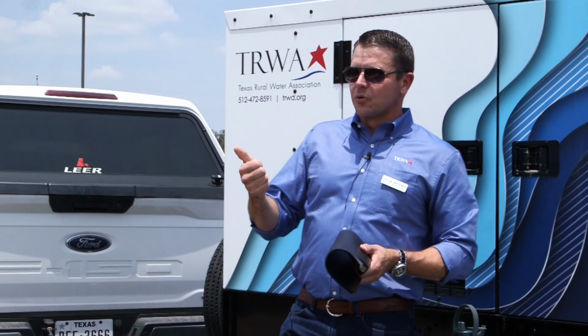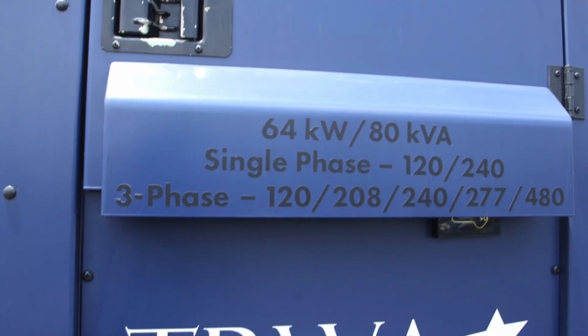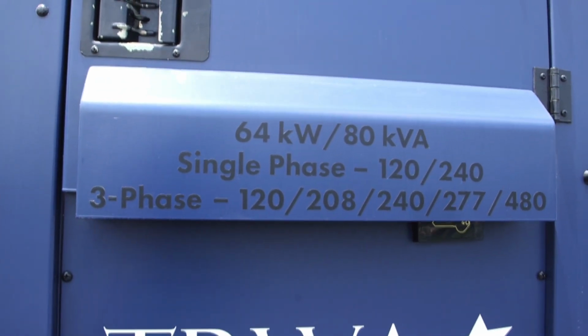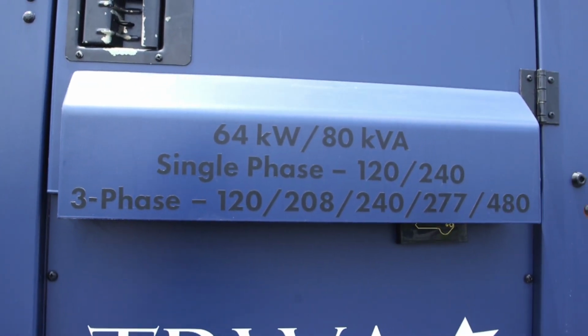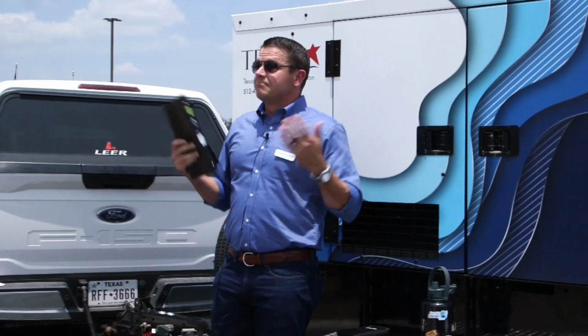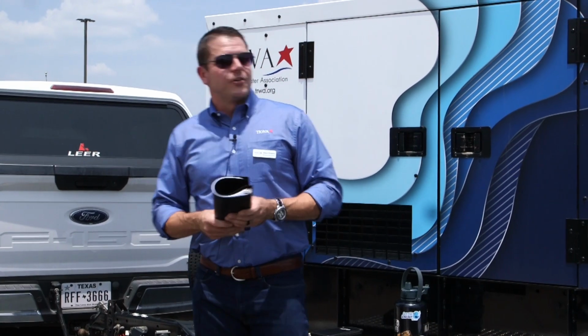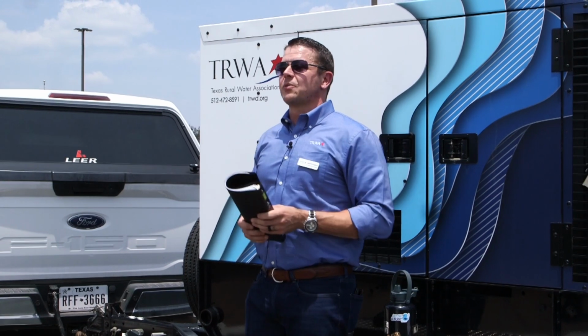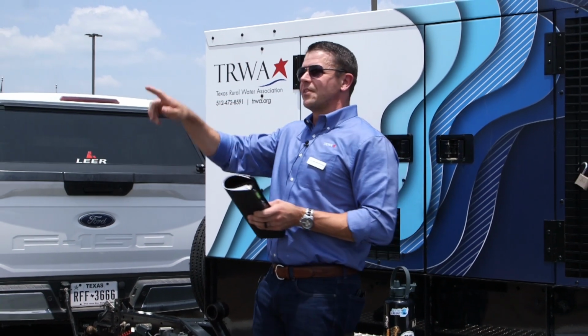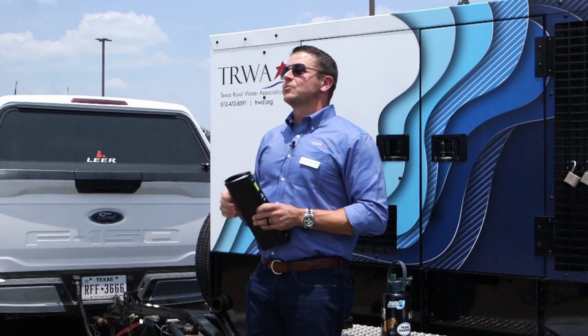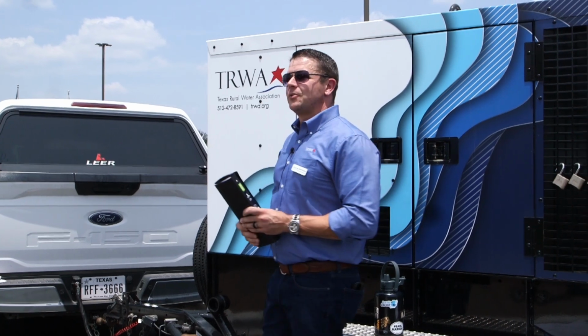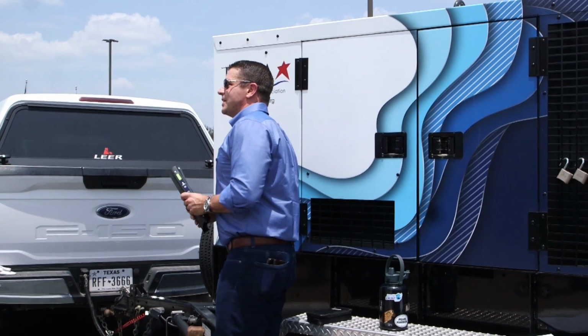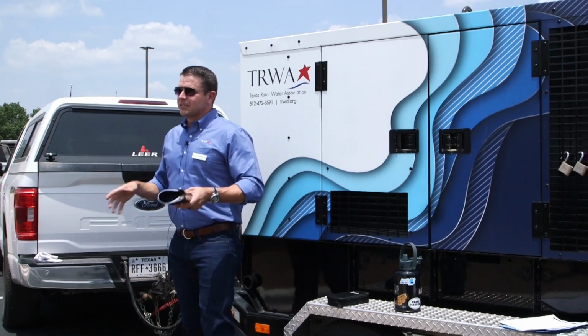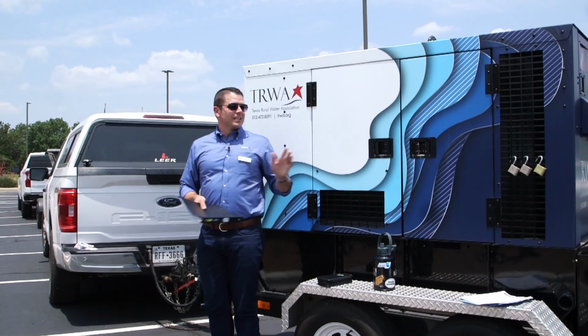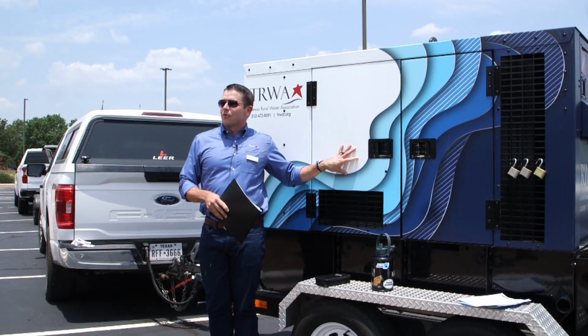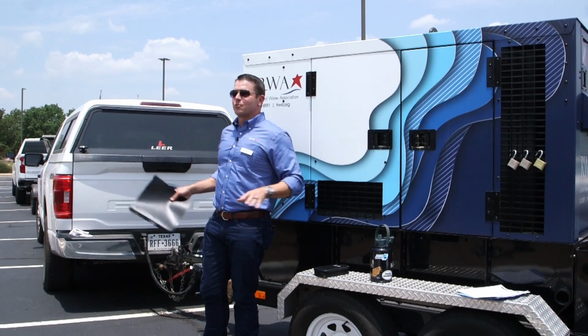So sizing is important. The voltage - we have on a couple of occasions showed up and they were very adamant. They said it was 480, so we applied 480. We turned it on, and you could look across the field in this wastewater system and see smoke coming from each one of the pumps. It in fact was 240, so we doubled the juice to it. That is one thing you don't want to do. You want to know your voltage, because now you're down not just because you didn't have power, but because none of your applications work.